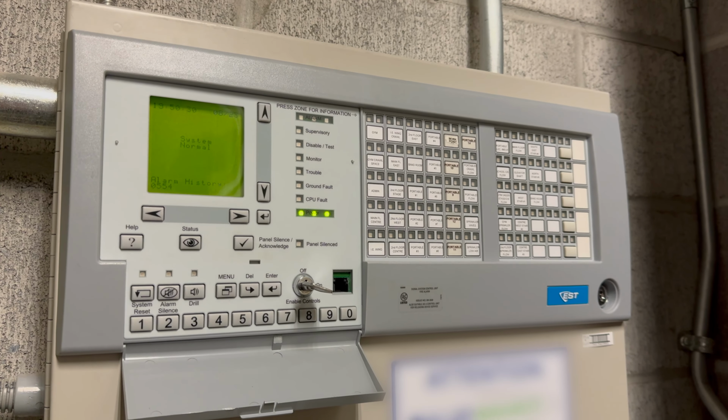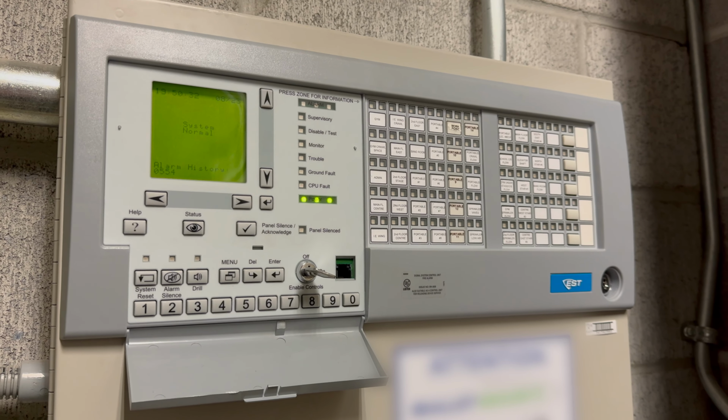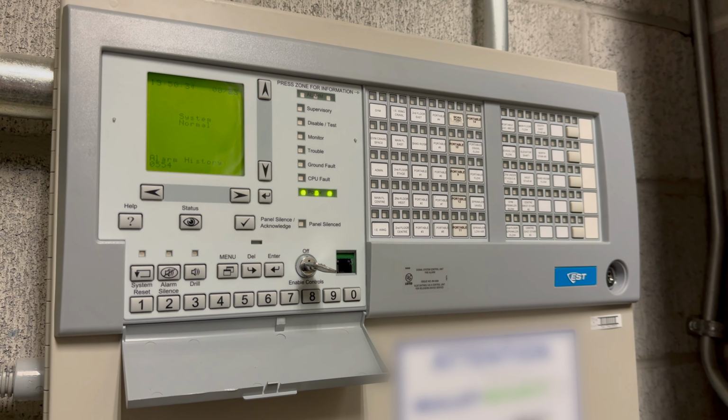This is probably the only one I'm going to show. We've done almost every other one. This one's just a little bit easier. So yeah, that's what we're going to be doing in today's video. We'll start by just letting the school know. We'll bypass bells, but just in case anything happens, they don't need to evacuate, and then call and put the system on test, and then give all the different conditions and make sure that the monitoring company is receiving the appropriate condition at the right time, that's labeled on their end as the right thing.